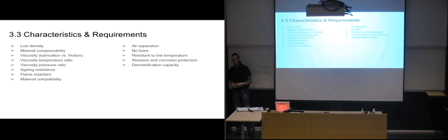Other things we also have to look at is air separation. We don't want bubbles to form, especially the cavitation kind. We don't want that. But also foaming and everything. We don't want foam to be created by the hydraulic fluid. It's not exactly a huge problem, but with air separation, you can get bubbles inside your system. So not the cavitation bubbles, the tiny bubbles that will do a lot of harm to your system, but with air separation, you can get larger bubbles of air, and air is compressible. So if you're trying to extend the piston by putting pressure into it, and you have a huge air bubble inside the piston, then you're just going to compress the air. You're not going to extend the piston at all.